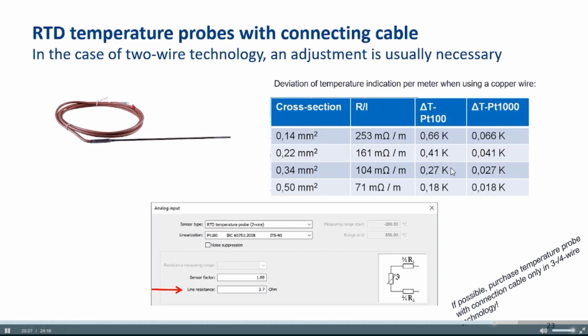How to find out the line resistance? You can look at the cable specification. If you know it, then you can find this value. But sometimes you don't have it, and then you need to make a correction measurement. You need to work with a reference device as well. This is complicated. I don't recommend working with such a cable probe with 2 wires. Please always buy these probes in 3 or 4 wire technology.